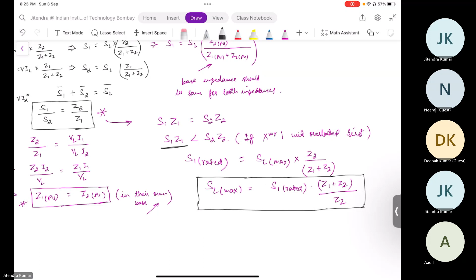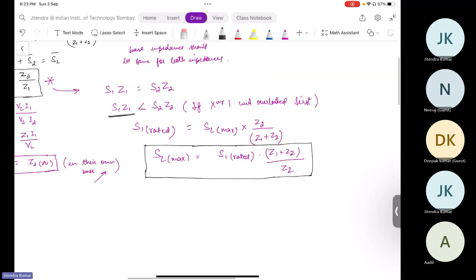If not, then I would like to complete this. Just for the sake of completion, I would like to write the similar scenario if S1Z1 is higher than S2Z2. It signifies that transformer 2 will be overloaded. In such a case, the maximum amount of load should be SL max equal to S2 rated into Z1 plus Z2 divided by Z1.